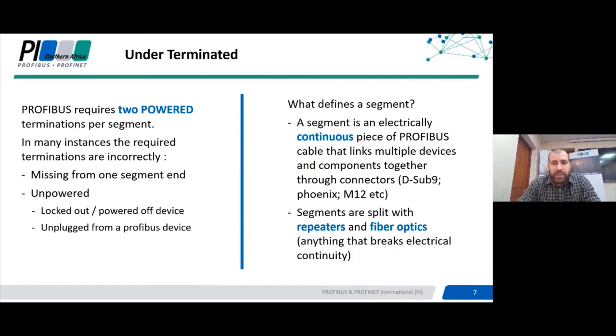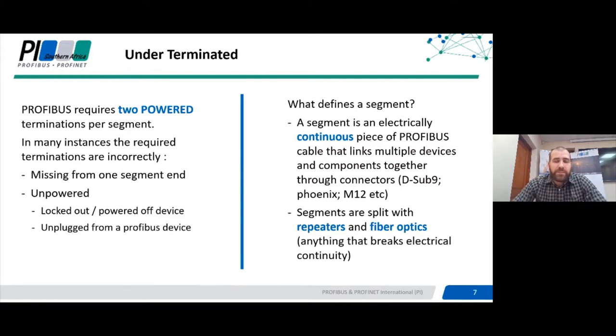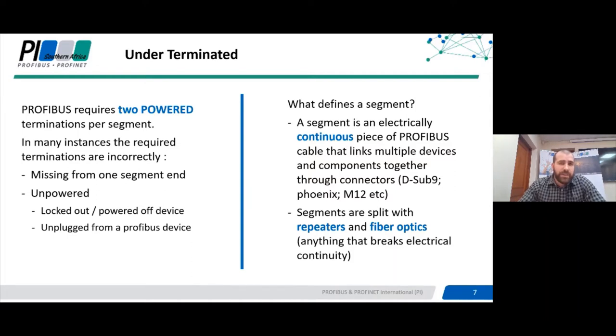When talking about signal quality, if you connect a high speed oscilloscope and look at the amplitude of the signal, it should typically be between 2.5 to 7.2 volts according to the specification. From experience, it should actually be less than 7 volts and more than about 3 to 4 volts. When it starts dipping below those values you're going to have issues. An unpowered termination is identified if the idle voltage is below 1 volt — then you obviously have an unpowered termination somewhere within the segment.